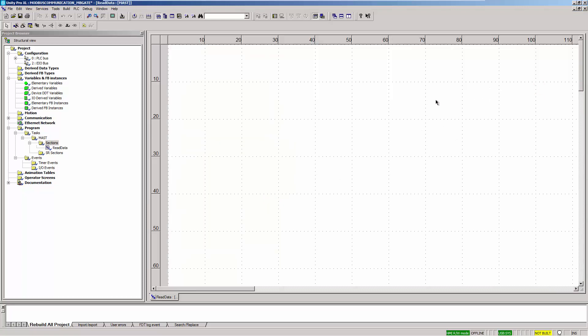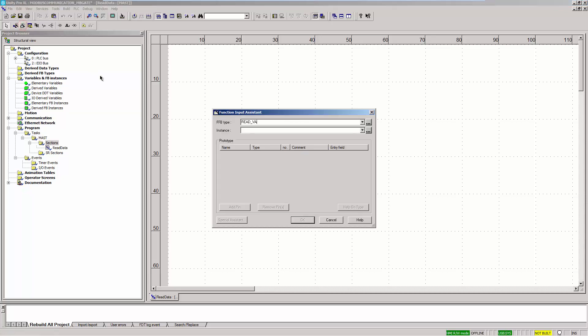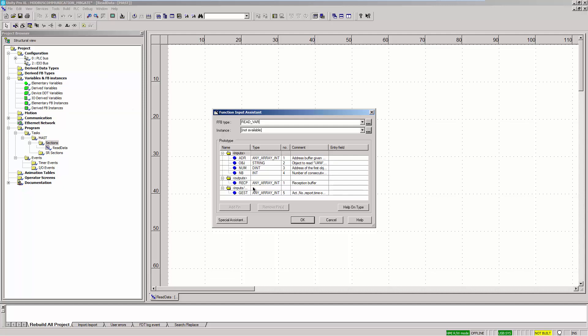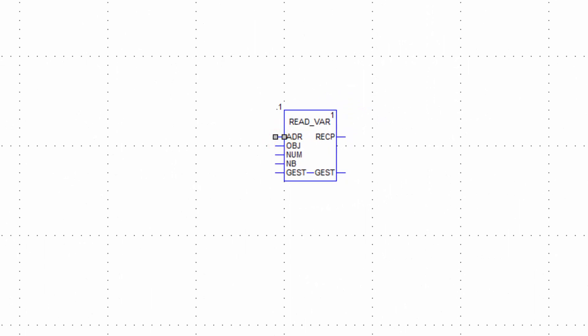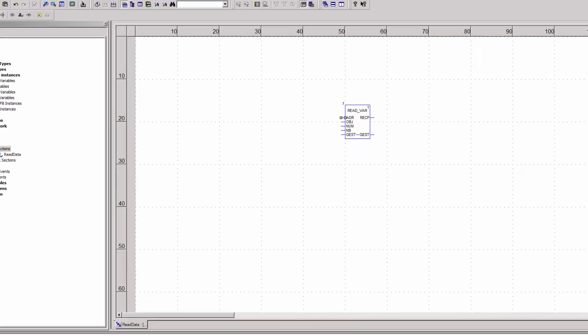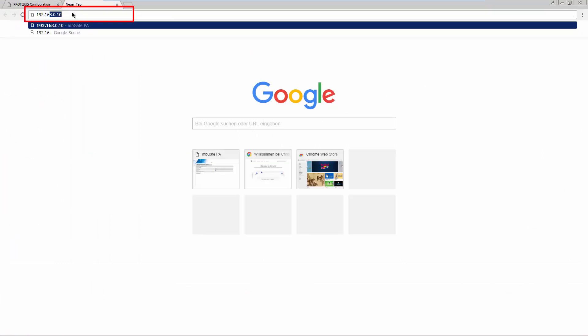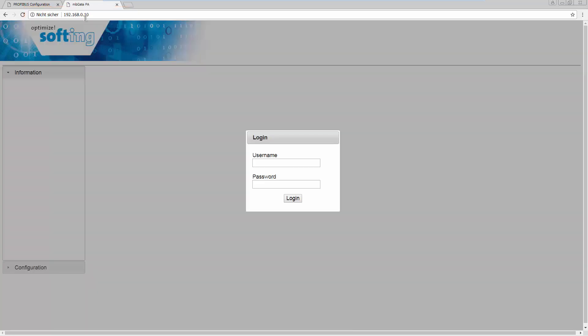Using the FFB input assistant, add a communication function READ_VAR. The address of the Modbus server must be entered in the ADR parameter. The IP address of the Modbus server of the MB-Gate PA can be found on its web server. In the internet browser's address line, write the IP address of the device. You will be prompted to log in with your username and password. You can find the login information in the user manual.